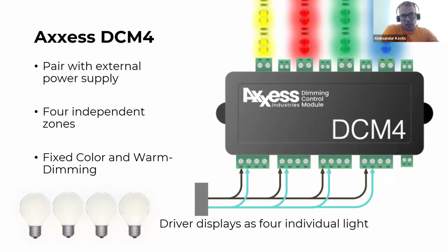DCM4 light channels. So when you use the driver for the DCM4 load and add it to the project, that light will appear as a lighting load in the user interface. So it is not like DCM3 or DCM5 that when you add it to the project, they immediately appear on the user interface as a controllable load. DCM4 by default is not visible by the end user. You need to connect additional drivers for each of the channels in order to control them from the user interface.